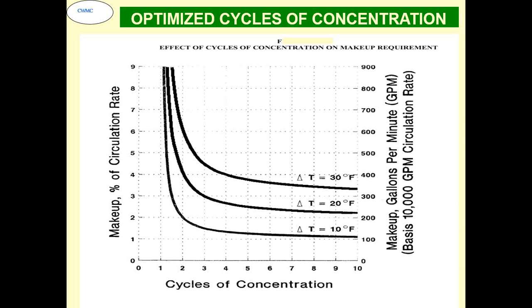There is very little change in the blowdown, because normally the treatments are based on the blowdown and the drift. So if the blowdown is reducing, there is hardly any change in the chemical that is to be dosed. So virtually 5 to 6 COC is the generally optimized thing.